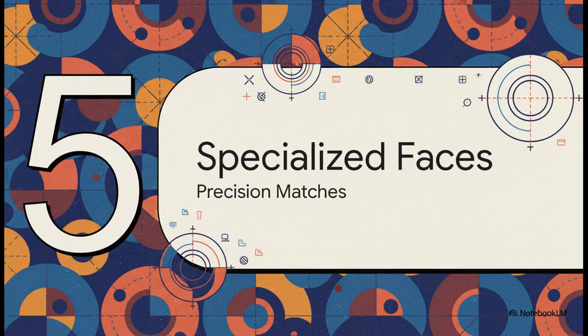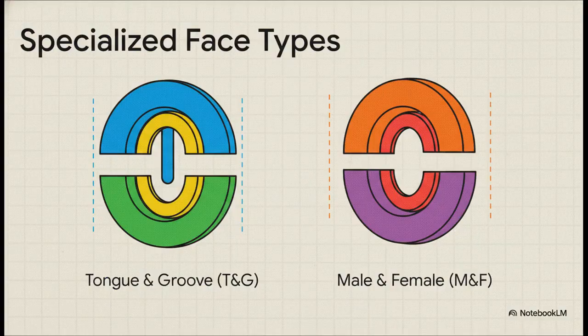And finally, Section 5, Specialized Faces for Precision Matches. Sometimes a flat or raised connection just won't cut it. Tongue and groove, as well as male and female faces, have to be used in matched pairs. They lock together exactly like puzzle pieces. A tongue and groove setup features a raised ring that drops right into a matching depression, which is absolutely perfect for lethal services like liquid ammonia, where you simply cannot risk a gasket blowout. Male and female faces work in a very similar way, but use a larger surface area lock, making them the standard for custom heat exchanger shells. Both of these designs are completely self-aligning and physically shield the gasket from corrosive external elements.